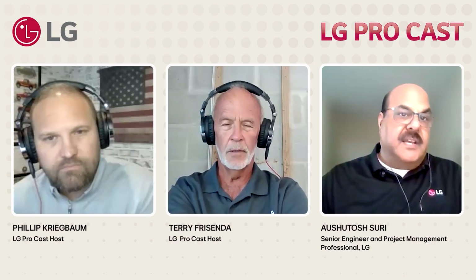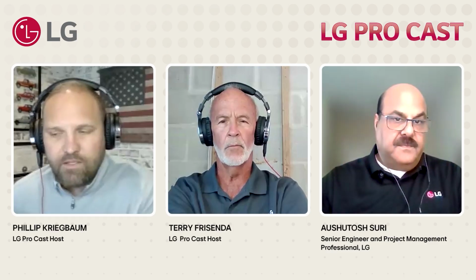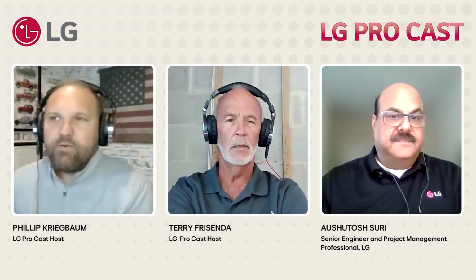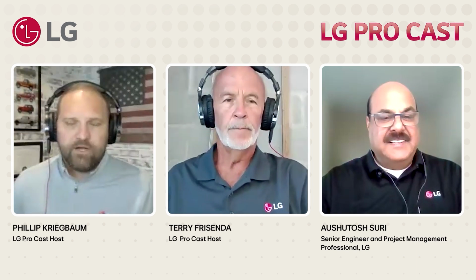So that's a very important point, which I think I discussed with Terry. Based on our requirements, the ducting, or how the system is laid out or the application, we can still do the manual setting as well. So you can have the manual setting with the values on your controller based on whatever ESP you want to set. If you want to be at 0.6 or 0.5, you can do that using the manual progression. But the factory would come with this feature as a default. I love that. To restate what he's saying, guys, if you're familiar with LG's air handlers, we've had this in the past where, in the old 410A, up to 3 tons, you didn't have to set the static pressure.